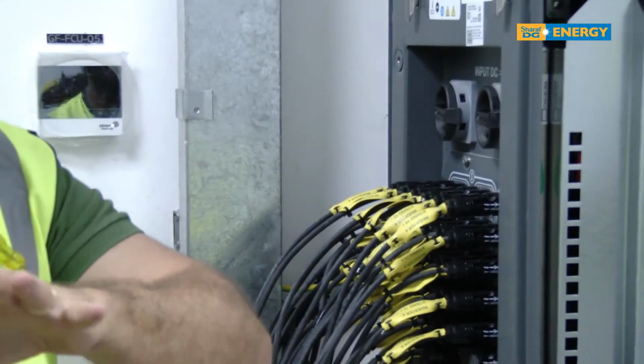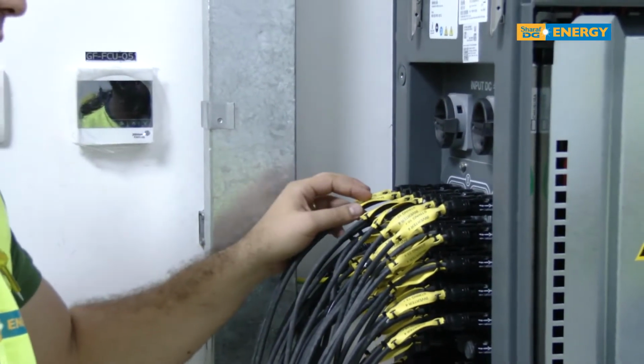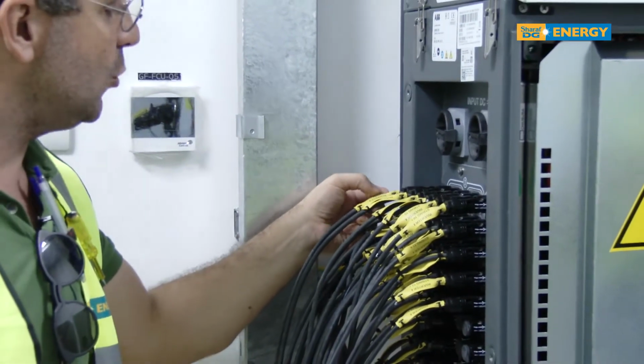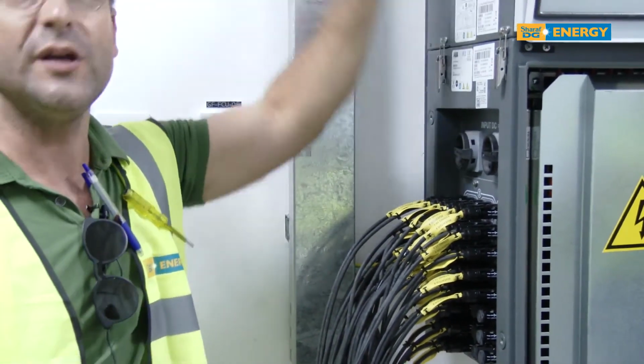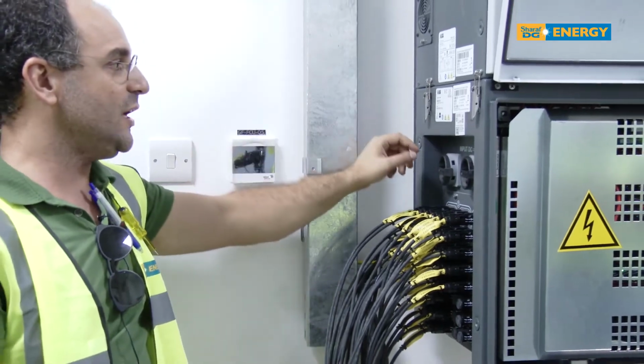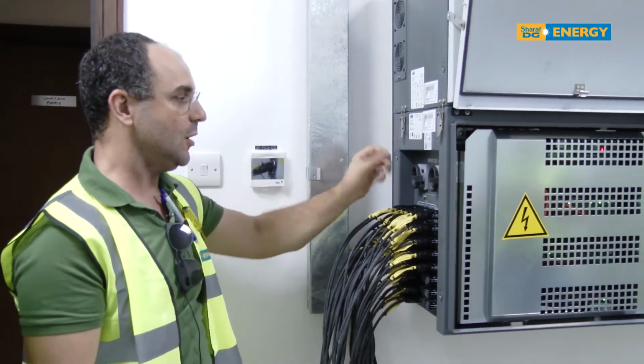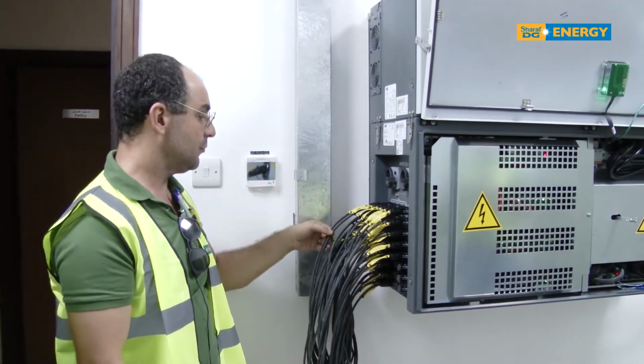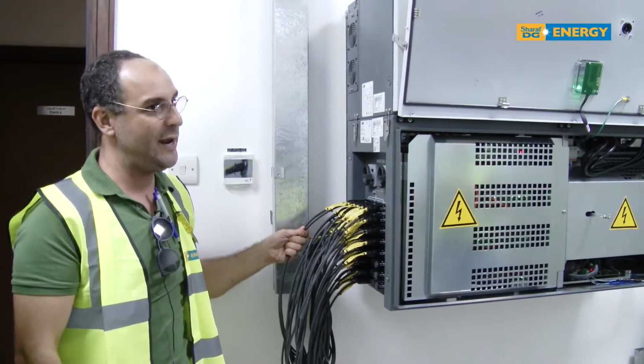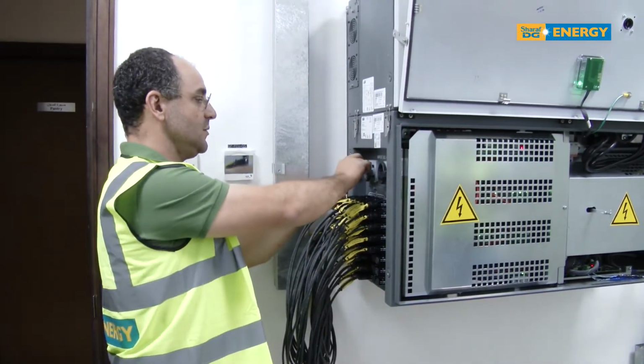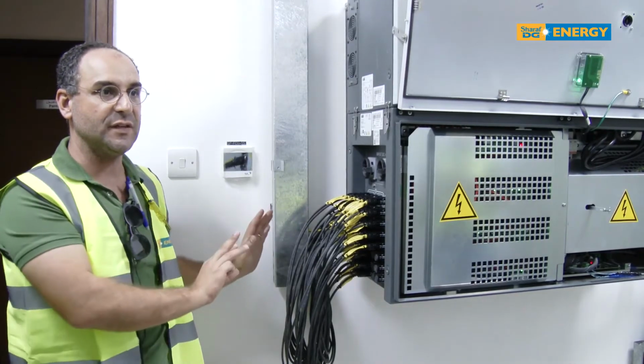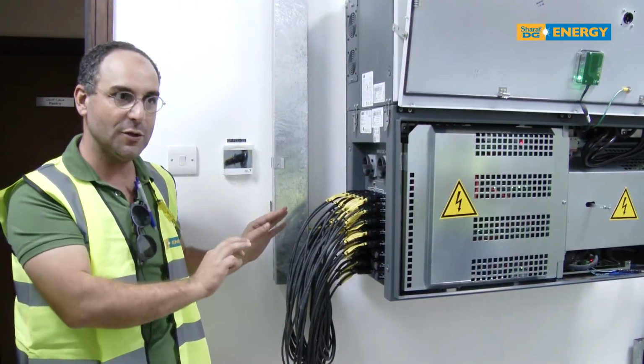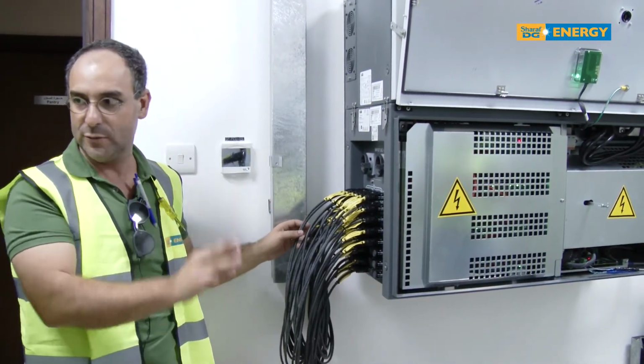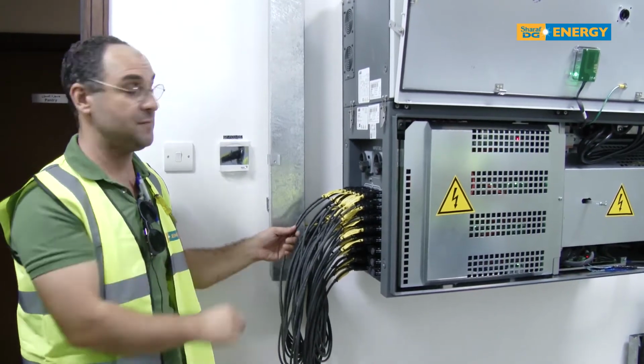But for yourselves, the same. Because imagine, string 1 inverter 4. Very good. We know the location. So we make sure that it's off, put the meter here, no amps, okay, so I can remove this safely and without sound. Don't worry, you will not see anything. No sound will come, nothing, because you have 0 amps, okay?